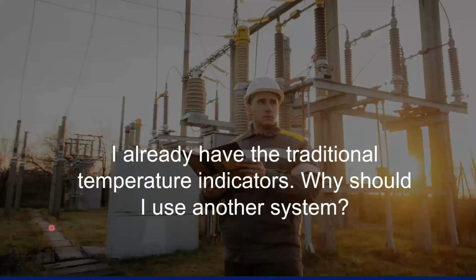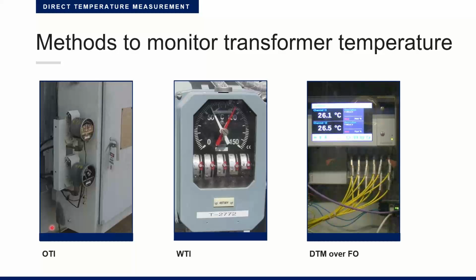Thank you. Yeah, but we have already traditional temperature indicators, so why should I use another system? That's true. I mean, it's nothing new if I tell you that temperature inside a transformer is important. Monitoring the temperature is nearly as old as the transformer itself. So let's have a look at a few methods which are available on the market for monitoring the temperature. You have on the left side the oil temperature indicator, which is just measuring the oil temperature inside the transformer. Then in the middle you have the winding temperature indicator, and on the right side you have the direct temperature monitoring over fiber optics. So the last two are telling you something about the temperature of the winding. So let's compare those two methods on the next slide.